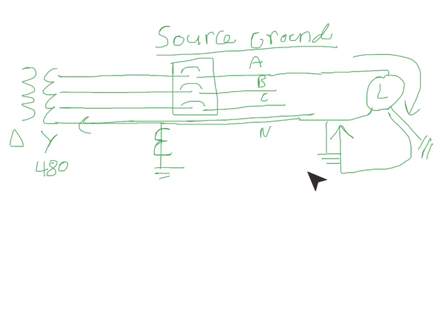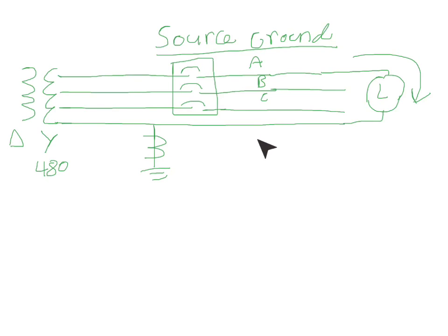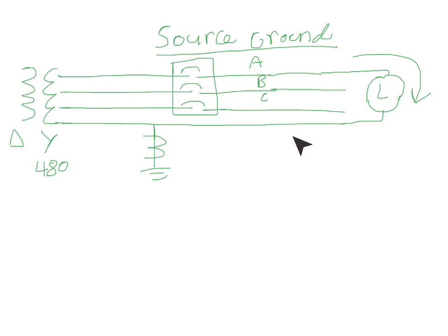So one way to check for that is you're going to want to disconnect this neutral bonding jumper link here and do an insulation resistance test between the neutral and ground. Like in residual ground fault, you're going to want to make sure that the system is not grounded on this side of the neutral here.